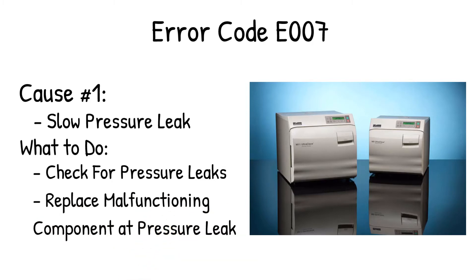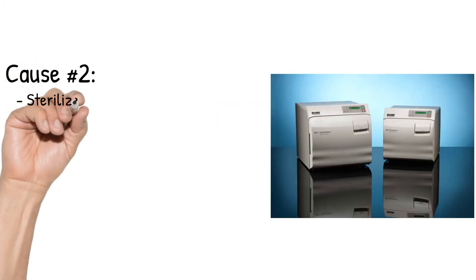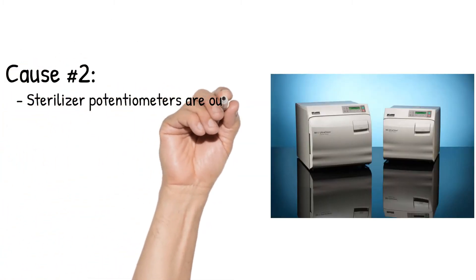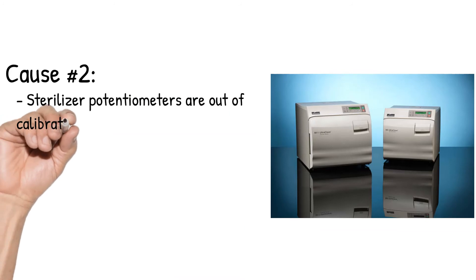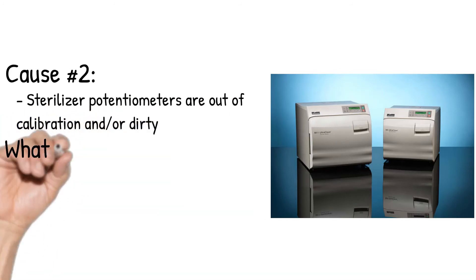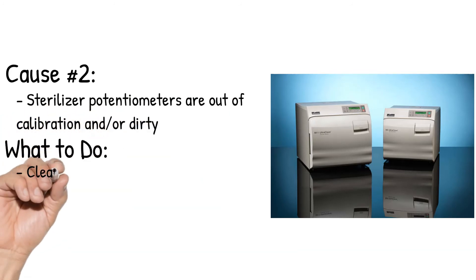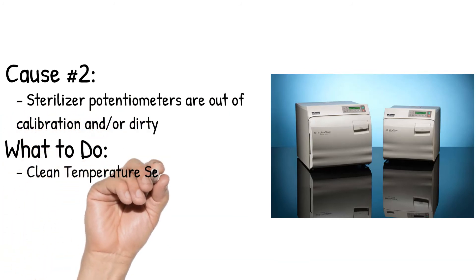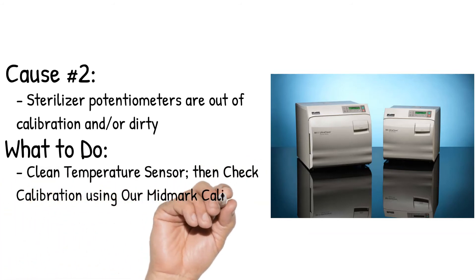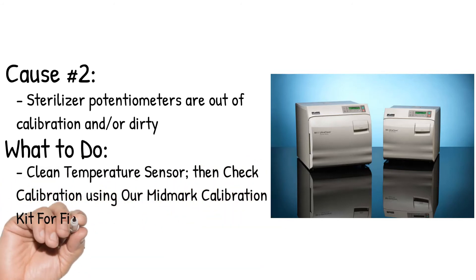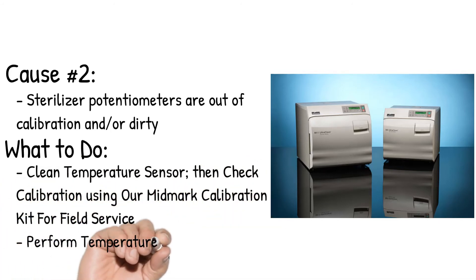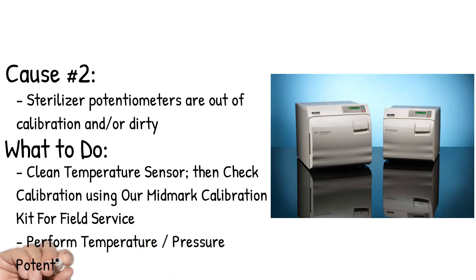Cause number 2: Sterilizer potentiometers are out of calibration and/or dirty. What to do? Clean the temperature sensor, then check calibration using the Midmark calibration kit for field service. Perform temperature and pressure potentiometer adjustment.